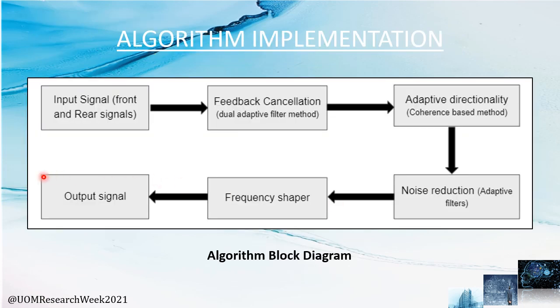Moving on to the algorithm implementation. In this block diagram, you can see the two input signals from front and back omnidirectional microphones. We use a dual adaptive filter method as our feedback cancellation method. After that, we use adaptive directionality to further enhance the input signal. Since we are using two microphones, the adaptive directionality method improves the signal by reducing noise. We also used an adaptive filter method for further noise reduction. After the noise reduction stage, we adjust the gain of the signal using a frequency shaper, and eventually deliver the output signal.